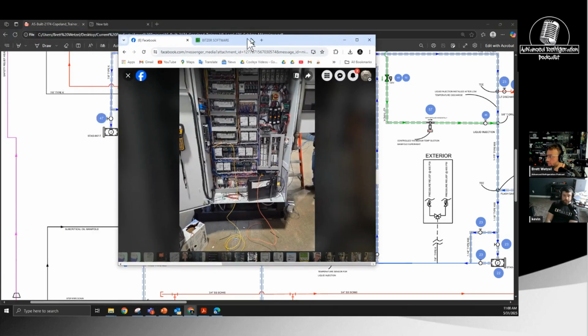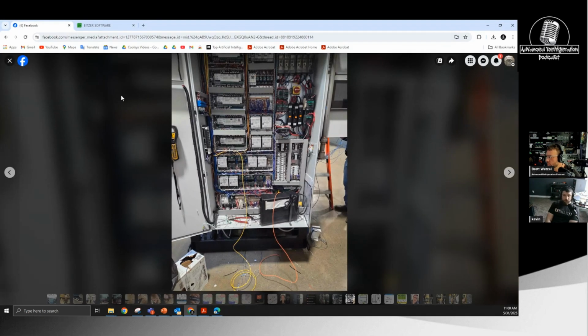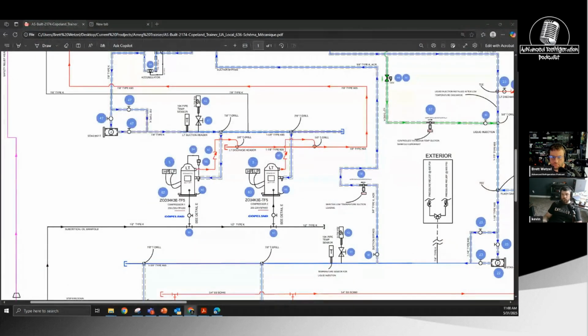So here's the control cabinet. This is in the midst of me rewiring some of this still because we converted. So they have these fixed stepper valve controllers in here for the Emerson CX valves, and the only ones left are the ones that control the actual EPRs and the liquid injection. We ended up switching out the rest of the evaporators for superheat controllers so we could actually change the superheat and give them a little bit more control, and show them on the actual E2 or E3, okay, this is what the valve driver is doing. There's a little bit more information on it and it's a little more intuitive.